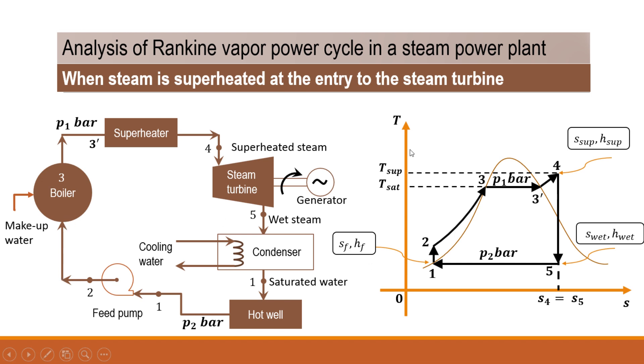The various processes are shown on the T-S diagram. Process 1 to 2 is pump work. Process 2 to 3 is the sensible heat supplied in the boiler. Process 3 to 3' is the latent heat of evaporation — at point 3 it is saturated liquid and at point 3' it is dry saturated steam. Process 3' to 4 is the heat of superheat supplied in the superheater. Process 4 to 5 is isentropic expansion in the steam turbine, during which entropy remains constant. The wet steam then enters the condenser, and process 5 to 1 changes the condition from wet steam to saturated water.